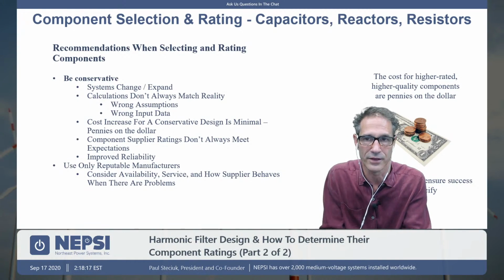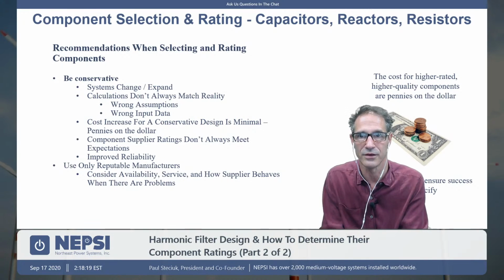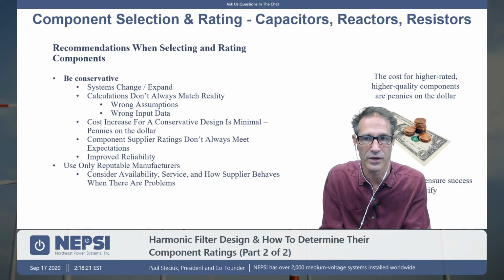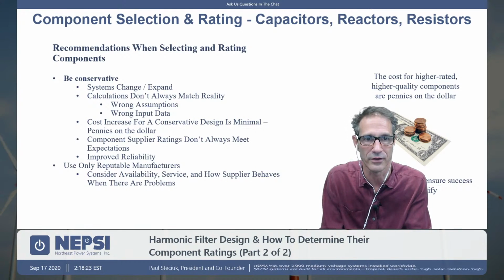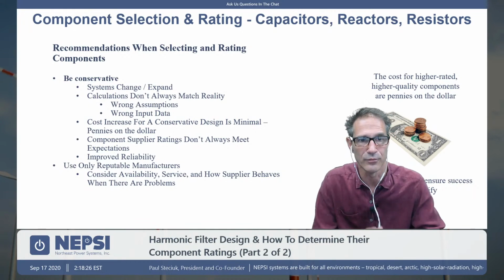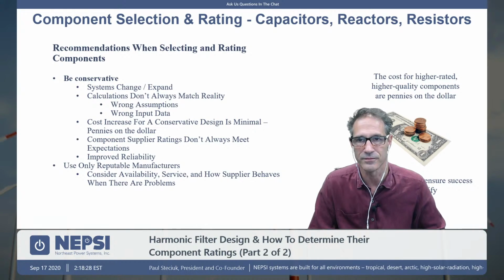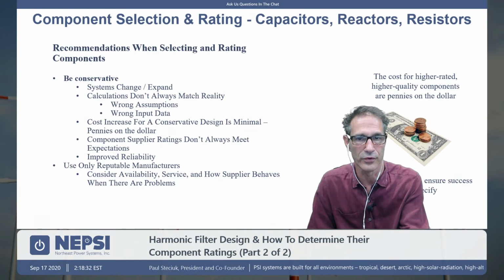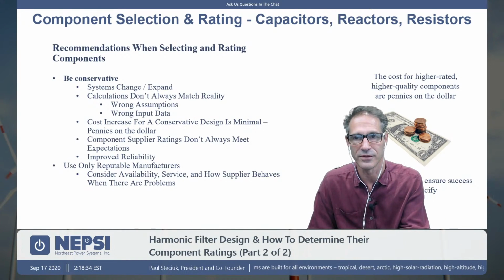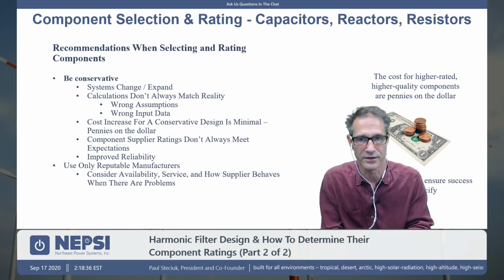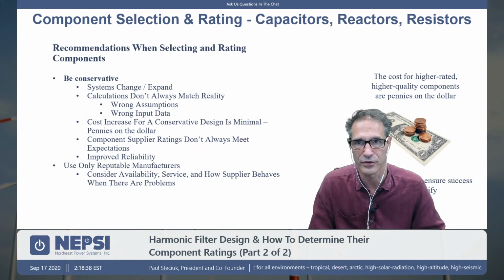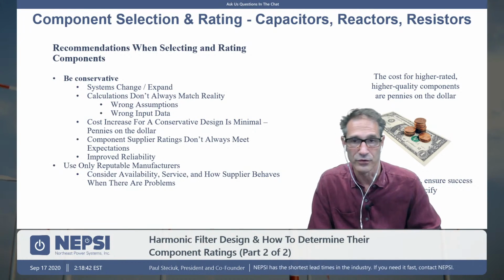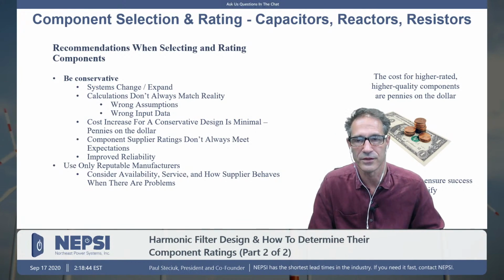That mine or that industrial facility might say, well, I want to expand. I want to add more drives. I want to add another compressor. I want to add another grinding mill. And that means more harmonic current to the system, and it might not necessarily mean that they need more reactive power. So you want to make sure that the filter design can handle that additional harmonic current that might become available in the future. If you don't, then the filter is at risk. It's at risk of burning up.